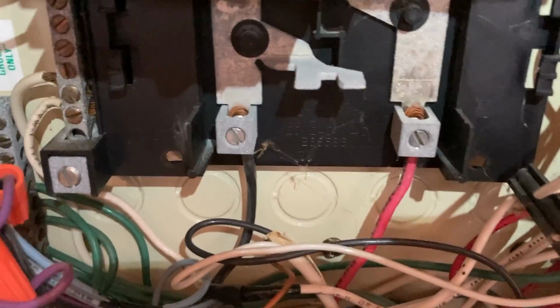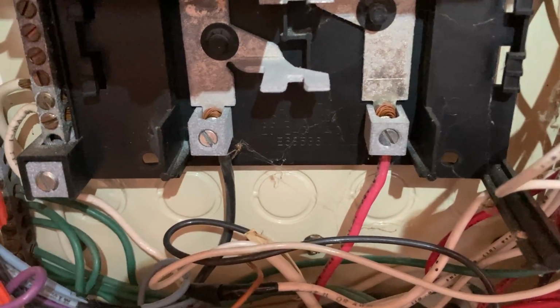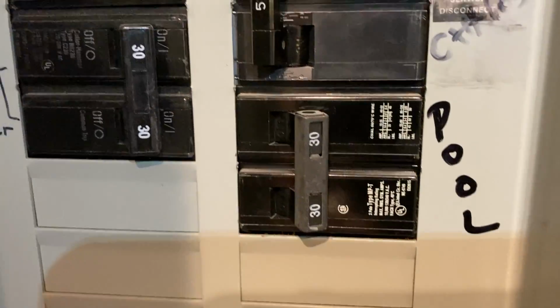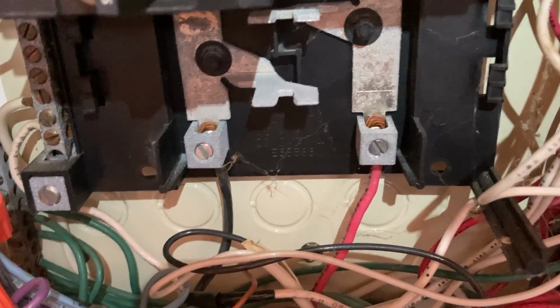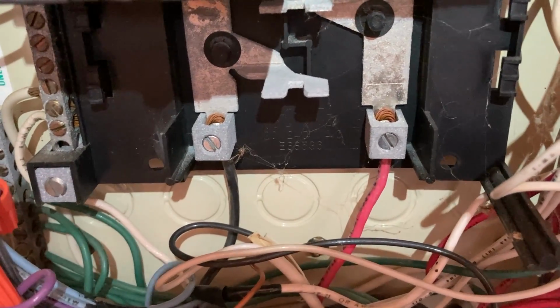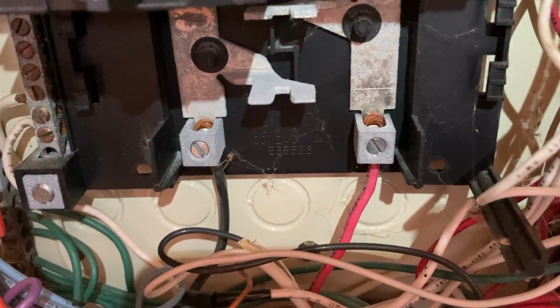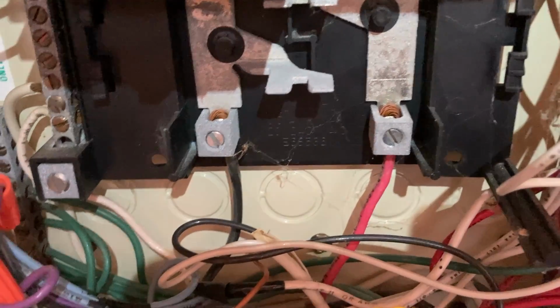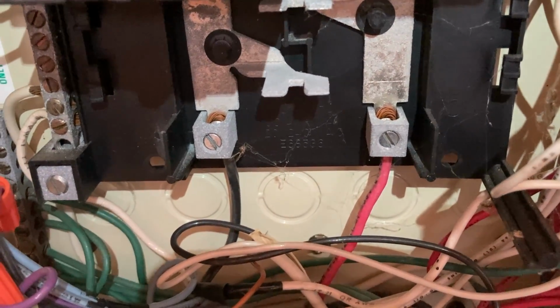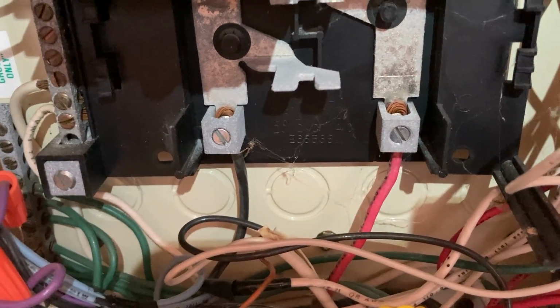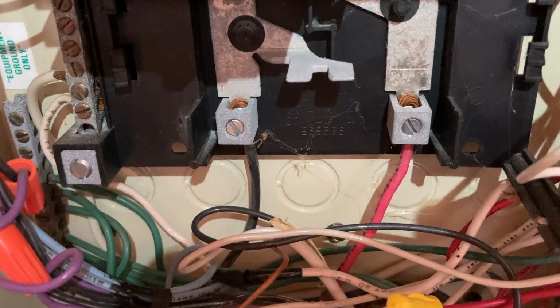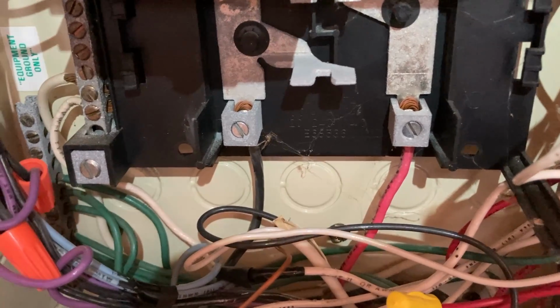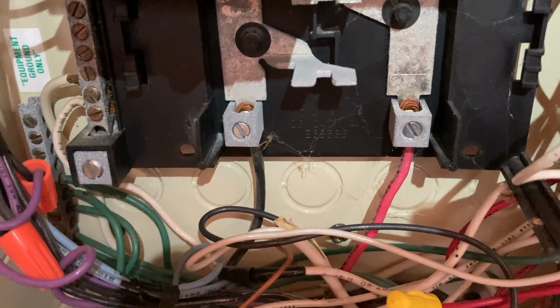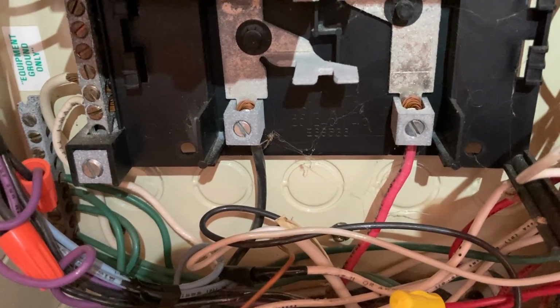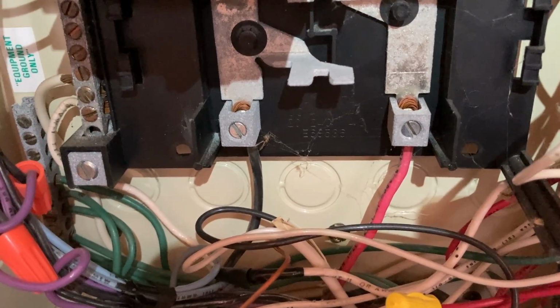So the bus in this panel board is fed with number 10 wire from a 2-pole 30 amp 240 volt breaker in the house, which is just about enough to do things. Half of that will go to the pump, the other half to the spa, and there's just a little left over for the other outlets and light, but that's not much of a load, or at least it's not used much. We may be going over a little if you plug a big drill or heater into one of the general purpose outlets, but this is a long pull under the cement on the patio, so upgrading this to like 50 amps just isn't gonna happen.